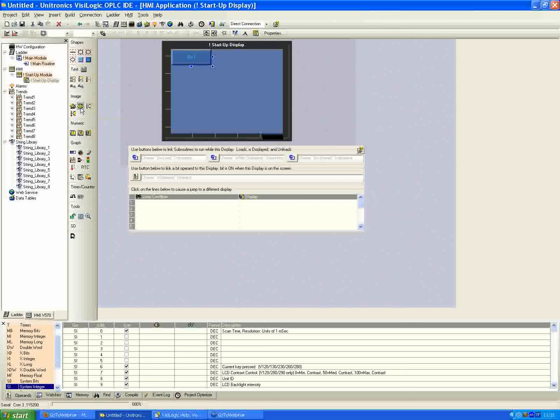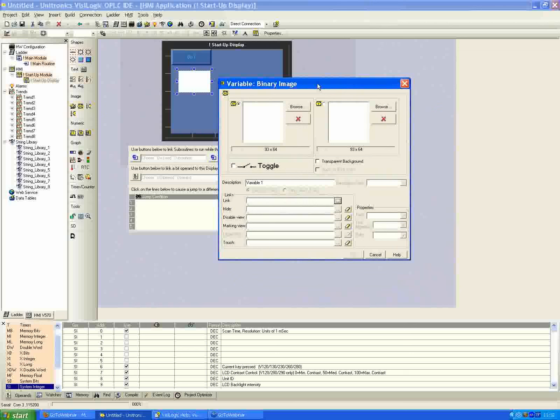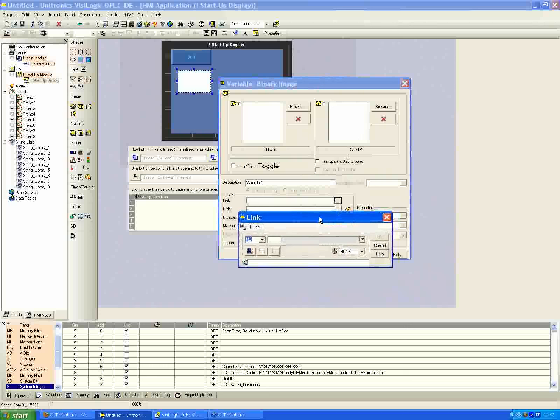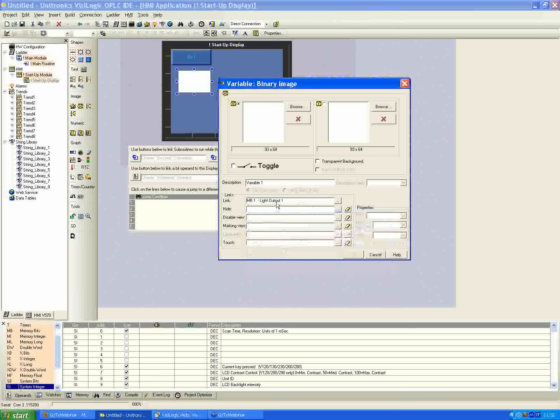Click this button, then hover over onto the HMI screen and you'll get crosshairs — hold down and draw out. Now the binary image window is open. This variable allows you to have two different states graphically represented. First, we want to link it to a Boolean value. Using the next available, we'll call it 'light output 1', so we have memory bit 1. You can see there's a 0 for the off state image and a 1 for the on state — depending on the high or low status of this memory bit, we display a different picture.